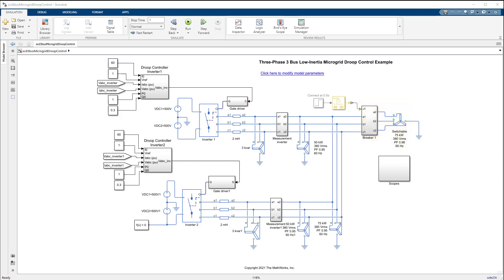A microgrid typically has a pre-planned load shedding strategy to reach balanced operations. Instant load shedding, however, is difficult to implement without a high level energy management system. This is where a simple droop controller can help maintain AC microgrid's frequency and voltages around their nominal values.